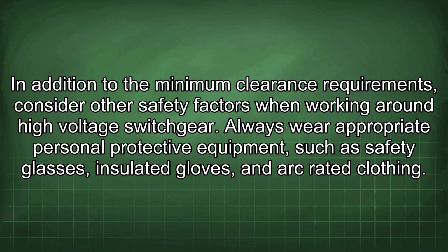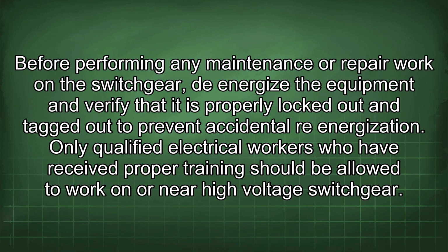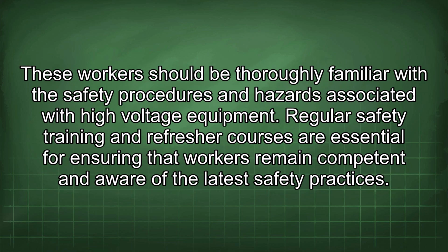In addition to the minimum clearance requirements, consider other safety factors when working around high voltage switchgear. Always wear appropriate personal protective equipment such as safety glasses, insulated gloves, and arc-rated clothing. Before performing any maintenance or repair work on the switchgear, de-energize the equipment and verify that it is properly locked out and tagged out to prevent accidental re-energization. Only qualified electrical workers who have received proper training should be allowed to work on or near high voltage switchgear. These workers should be thoroughly familiar with the safety procedures and hazards associated with high voltage equipment.